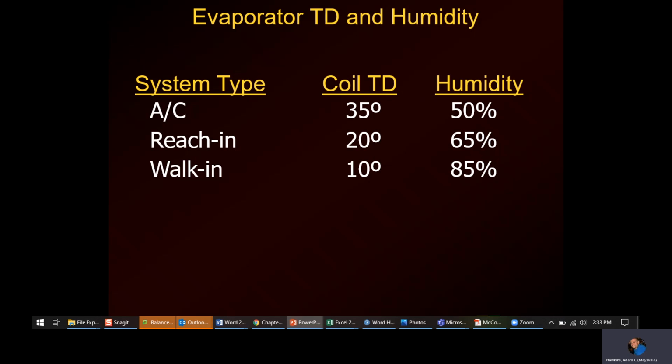All right. So, like I said, without getting too far into commercial type setup, AC, we're usually trying to operate under a 35 degree TD with a 50% humidity in the house. That's kind of normal operating conditions. So not only are we concerned with the temperature of the room, we're concerned with conditioning the air. We're concerned with the comfort of the room.